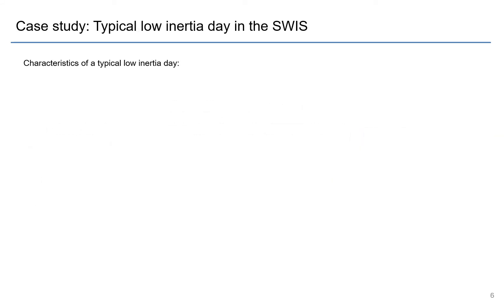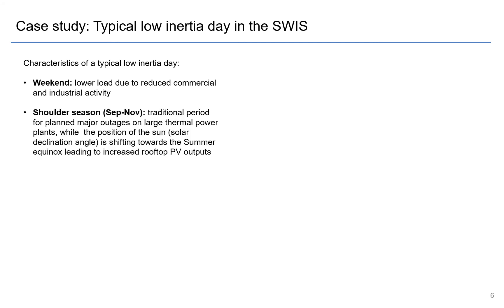So what makes for a typical low inertia day in the SWIS? Low inertia is strongly correlated with low loads. Low loads occur on weekends, when there is reduced commercial and industrial activity, and during shoulder periods — for us, September to November, the spring shoulder. That's traditionally the period for planned major outages on large thermal plants. At the same time, the solar declination angle is shifting toward the summer equinox, so we see increased rooftop PV output. With major outages reducing inertia and high PV output eating into operational demand, conditions align for very low inertia.